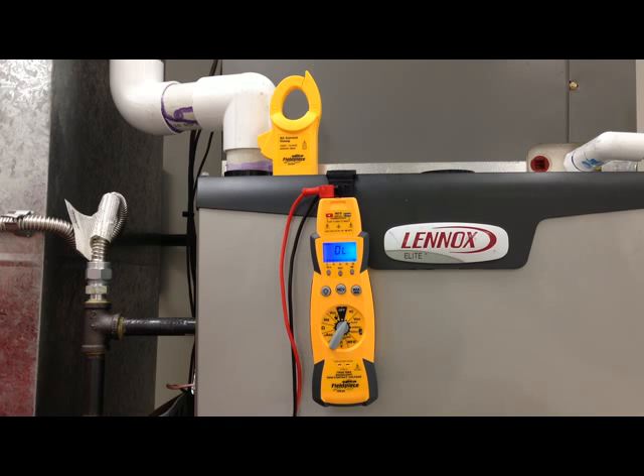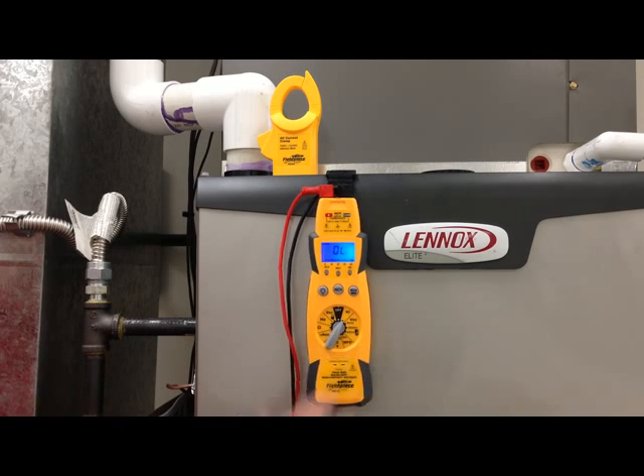The continuity tester can be used to check a wire to see if a wire is broken, to check a coil to see if the coil of wire is good. One word of caution, don't become overconfident on the continuity tester. It only tells you that one of the wires is good. If we're using a stranded wire that's made up of multiple strands within one jacket, that could only mean that one wire is good. The others could all be broken and not be able to carry the current that you need.